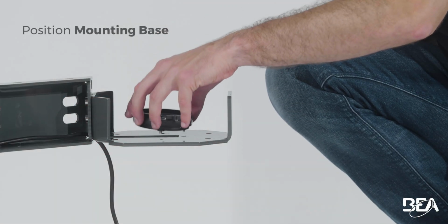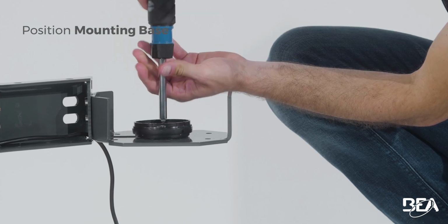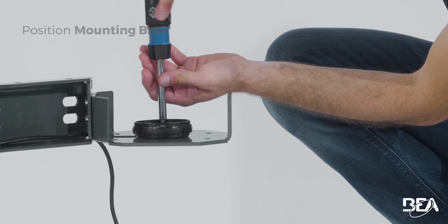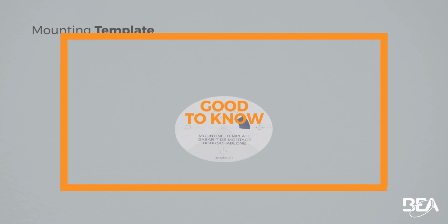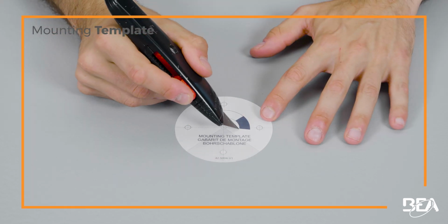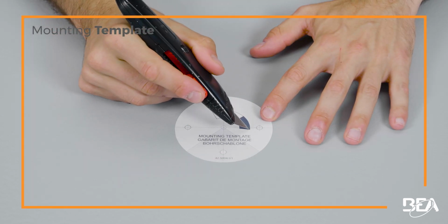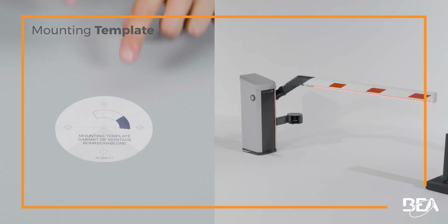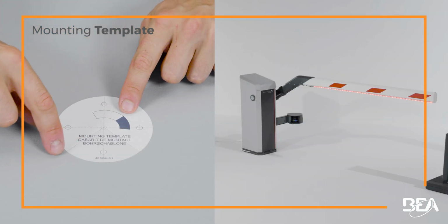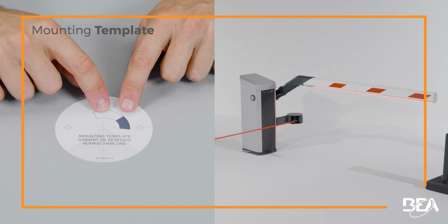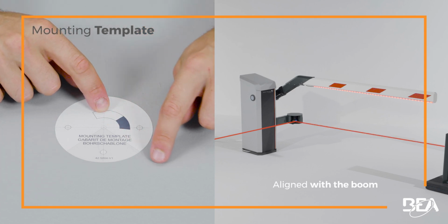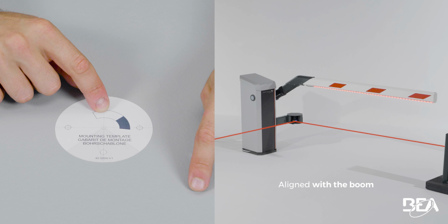Position the mounting base on the bracket and fasten the four screws firmly to avoid vibrations. If needed, you can use the mounting template. Cut a hole in the mounting template to pass the cable. The limits of the grey zone represent the 0 degrees and 90 degrees visible laser beams. Make sure the left limit is aligned with the boom.